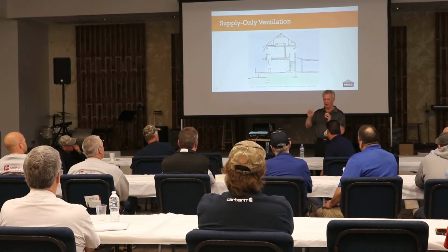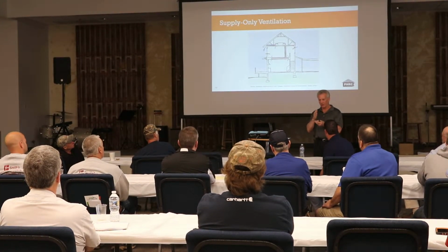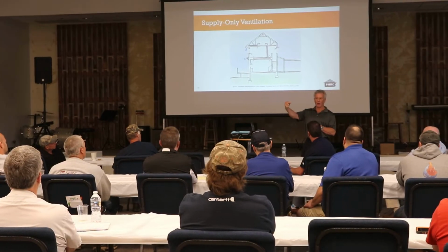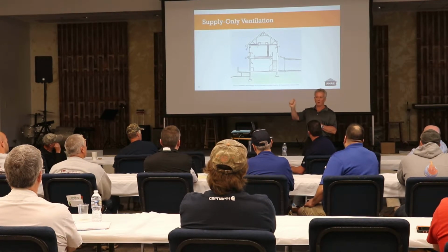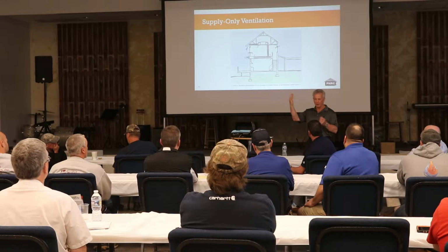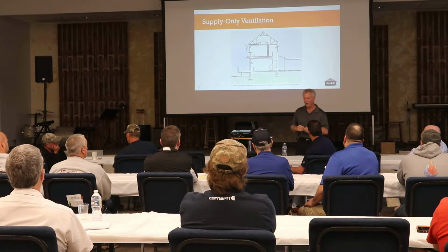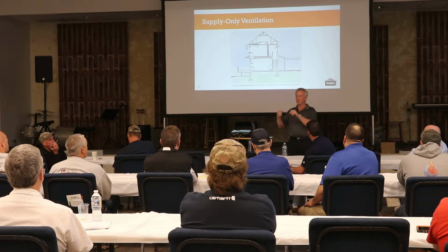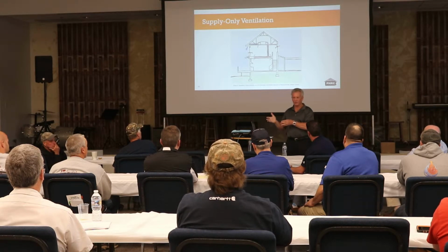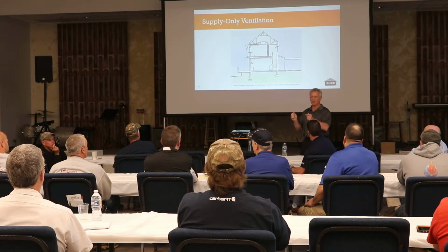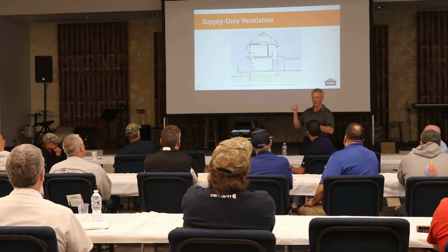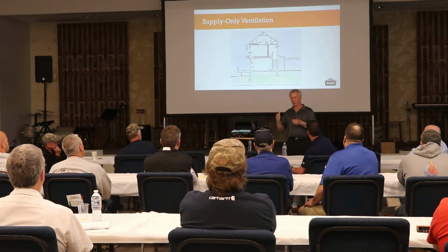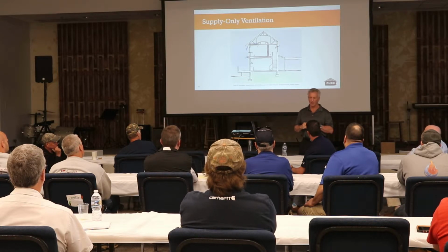So when you're doing this basically on the 25% intermittent usage, that's multiplying your requirement by 4. So if we're at 45 CFM, you're now up to 180 CFM in that case. So what are you relying on to pull the air out? You just add exhaust? Okay. But that's much more random, that's the one thing about this method. You don't have a predictable balancing effect if you're relying on bath exhaust in that case.